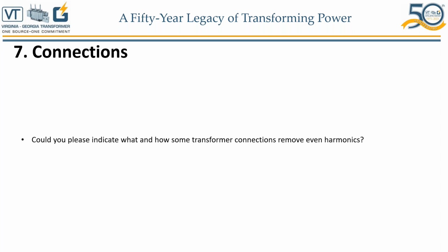Harmonics are distortions in the voltage and the current waveforms, and they are caused by nonlinear loads, such as electronic devices, variable speed drives, or arc furnaces. And these harmonics actually create overheating and insulation degradation. We can use rectifier circuits, and these are explained not only in our presentation, but also in C57.18.10. In that IEEE guide, it shows the proper connections of the more common circuits. So some of the answers you may find in C57.18.10.